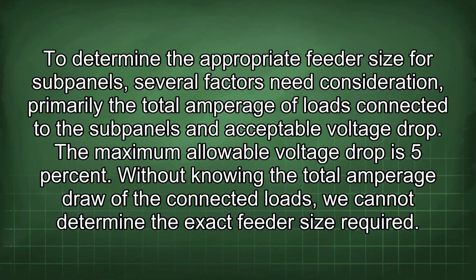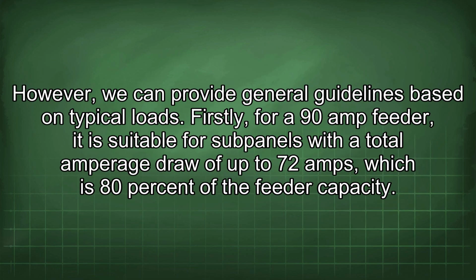To determine the appropriate feeder size for subpanels, several factors need consideration, primarily the total amperage of loads connected to the subpanels and acceptable voltage drop. The maximum allowable voltage drop is 5%. Without knowing the total amperage draw of the connected loads, we cannot determine the exact feeder size required. However, we can provide general guidelines based on typical loads.